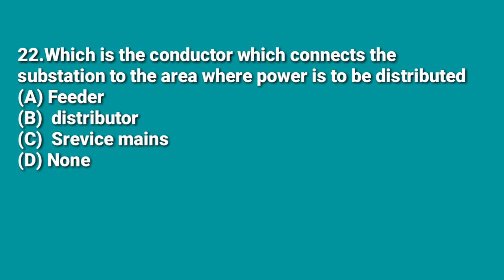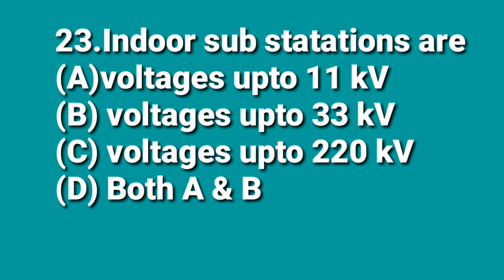The next question: which conductor connects the substation to the area where power is to be distributed? The answer is feeder — the conductor that carries power from a distribution substation to the distributor is a feeder. The following question: indoor substations are used up to which voltage? Indoor substations are used up to 33 kV; substations more than 66 kV may have insulation problems, so B (up to 33 kV) is the correct answer.